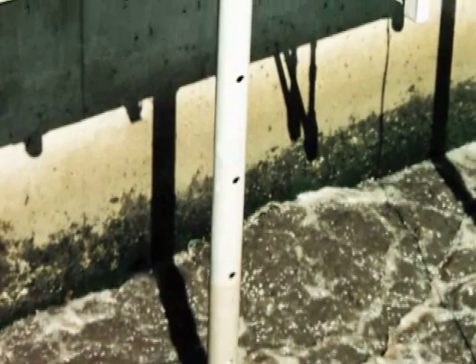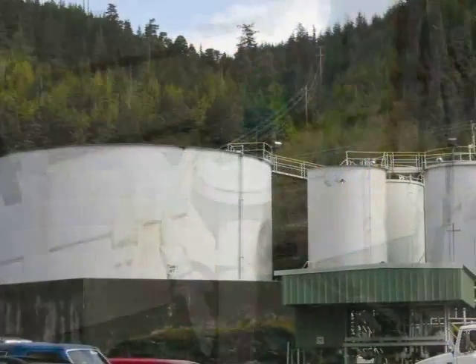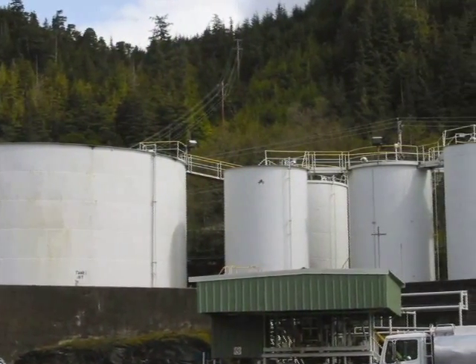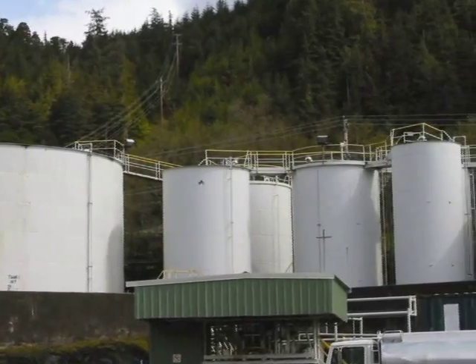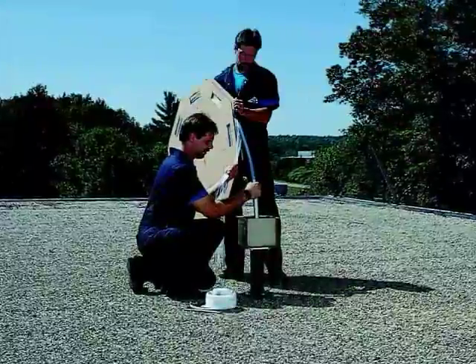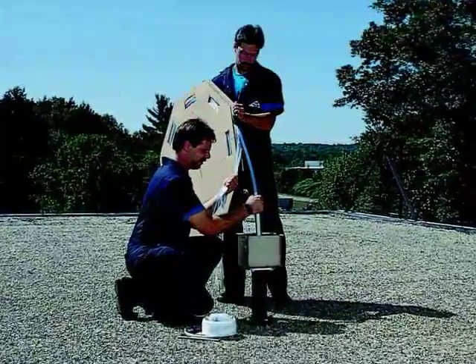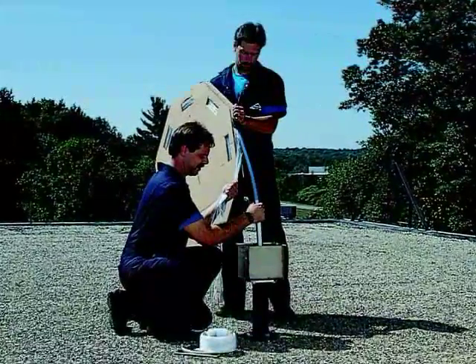In this picture, we show an AquaTape installed inside a steel pipe measuring agitated wastewater. For oils, crudes, and refined products as shown in this tank farm picture, PetroTape is well-suited. Here, the optional internal temperature sensor can be attractive. These flexible level gauges are easily installed from the tank top into a steel pipe, or for non-agitated tanks, a specially weighted sensor can be used without a steel pipe.